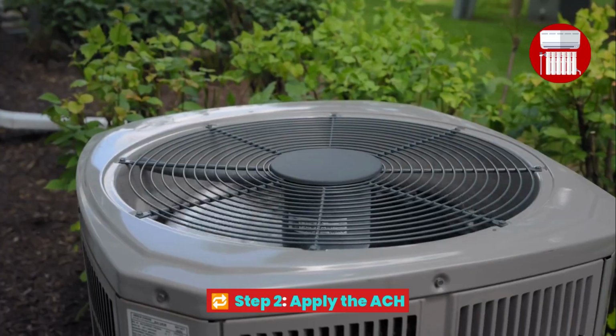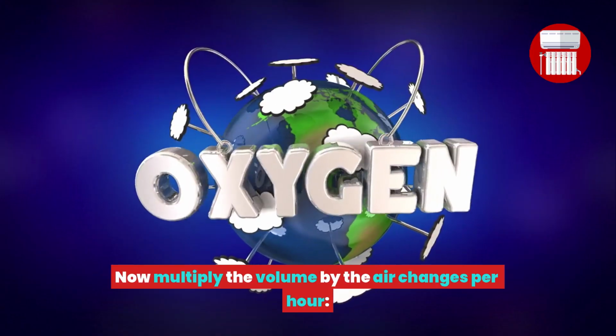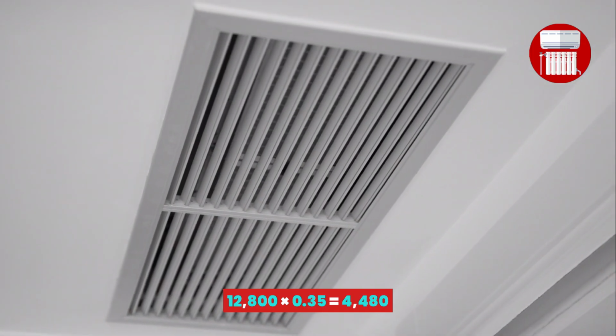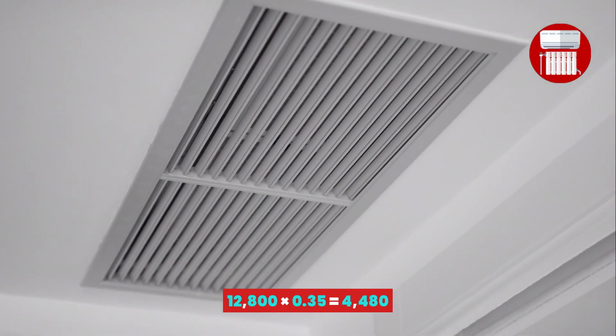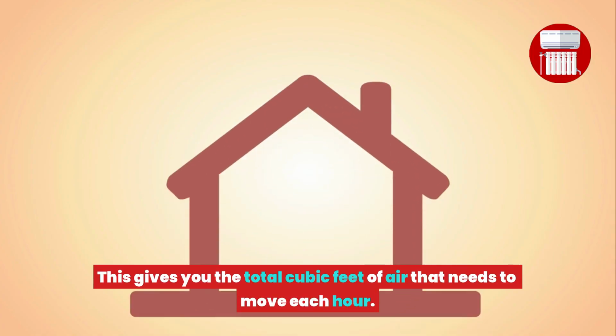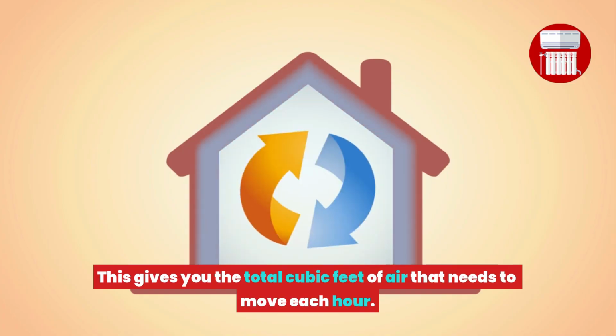Step 2. Apply the ACH. Now, multiply the volume by the air changes per hour. 12,800 times 0.35 equals 4,480. This gives you the total cubic feet of air that needs to move each hour.